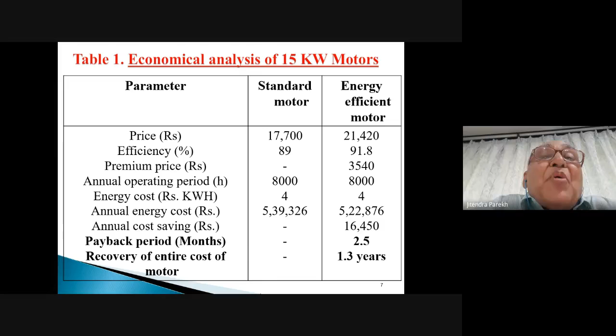Also, we are using a lot of VFDs, and sometimes we are using throttling valves. Throttling valves have some problems compared to variable frequency drives, which, in conjunction with pressure and flow measuring devices, can automatically vary the speed of pumps, fans and compressors to suit the actual load requirements. These are much more economical than throttling valves for regulating flow. The energy saving potential of a 30 kilowatt VFD I have shown in my next slide.